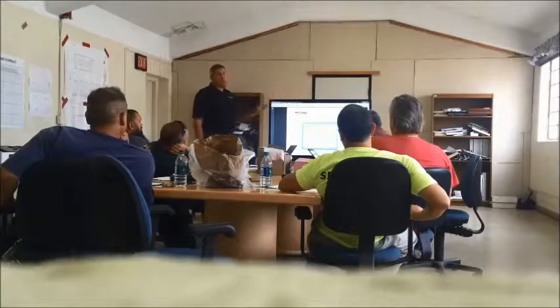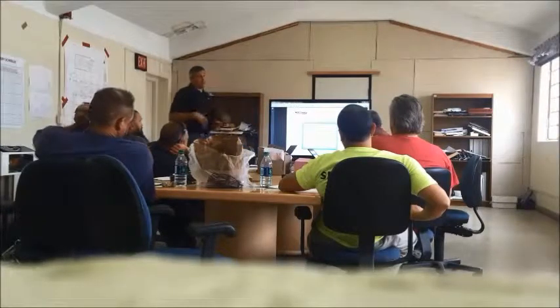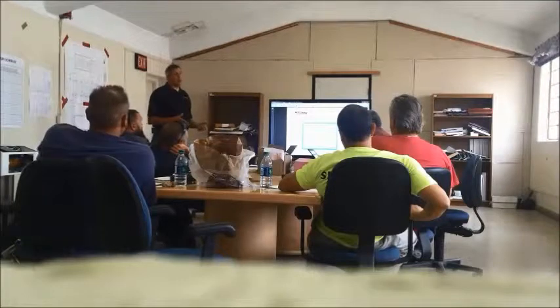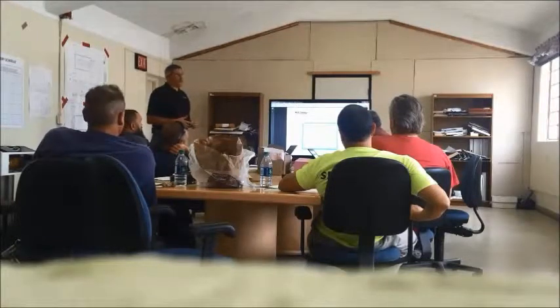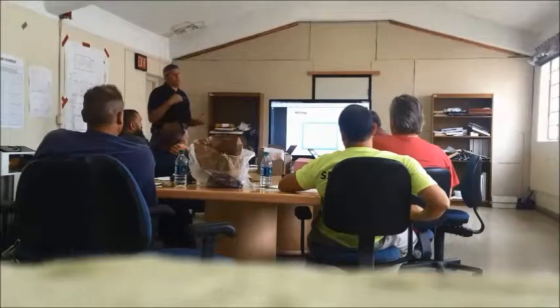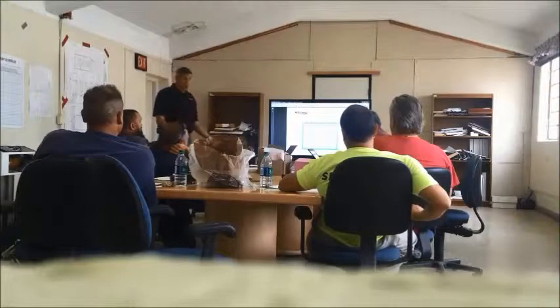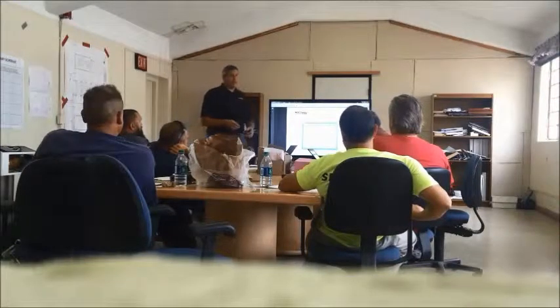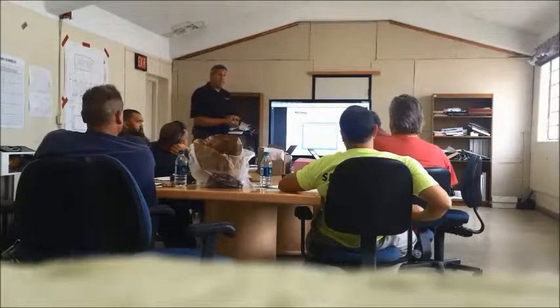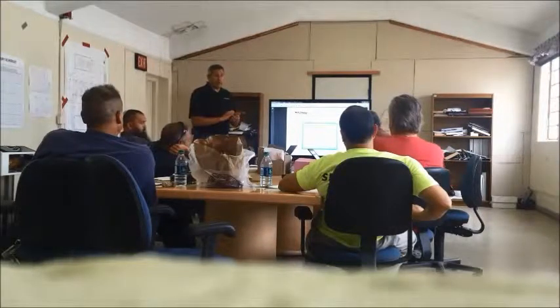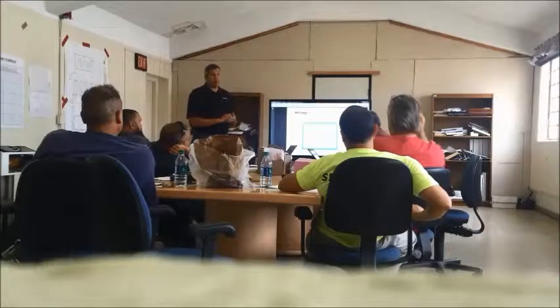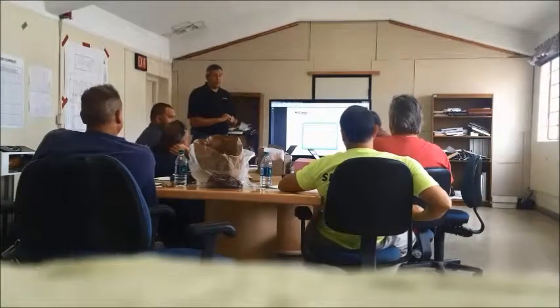We'll show you. So under its normal condition, it runs at 1.5 inches of water column under a standard operating set point, and then once it gets an input from the fire life safety system, if there's a fire event, then it'll force it because it has a higher priority. As you were programming, that's what I'm trying to understand: this input, is it hardwired from the fire system? Yes, it's directly hardwired from a fire life safety module directly to the controller input. That's correct.